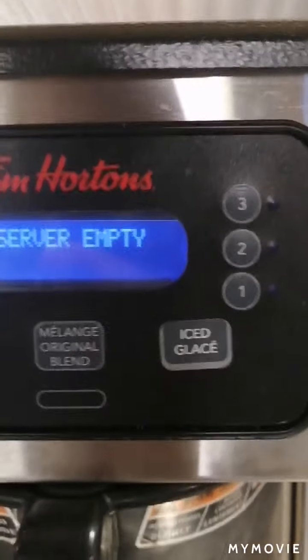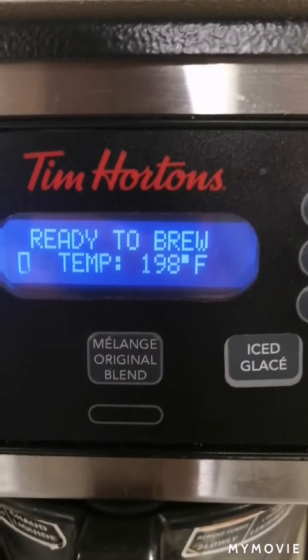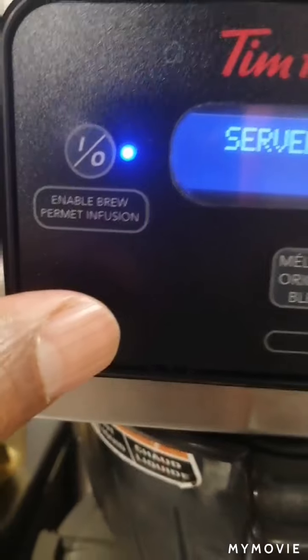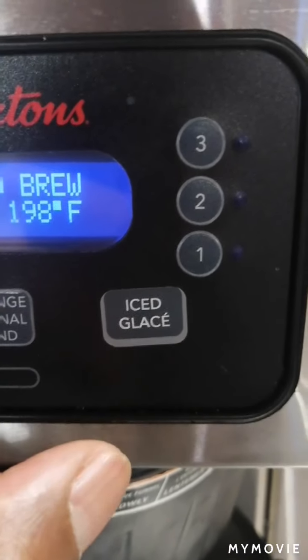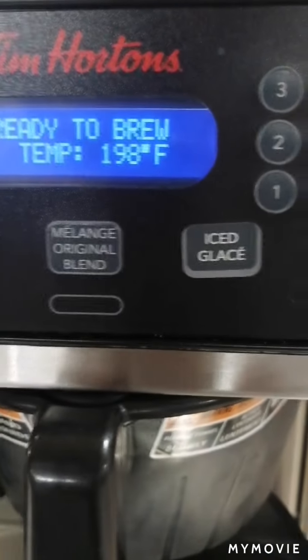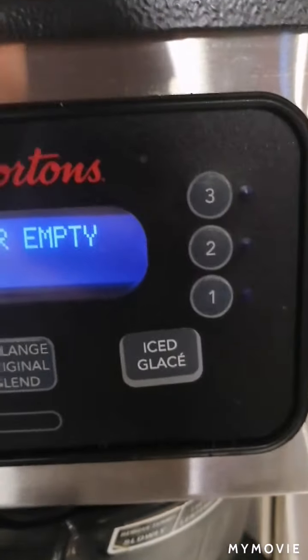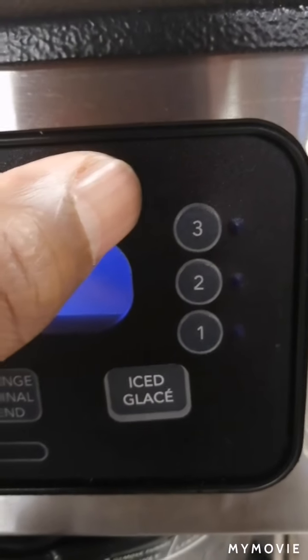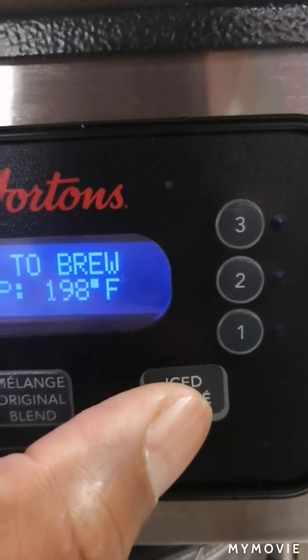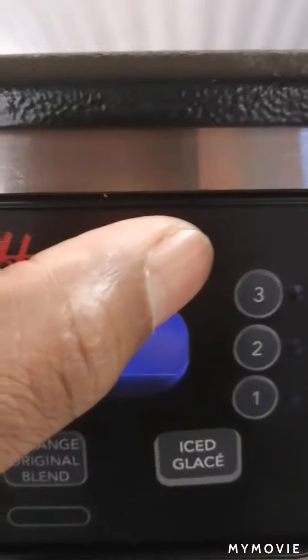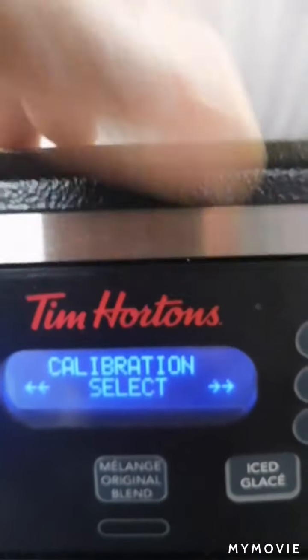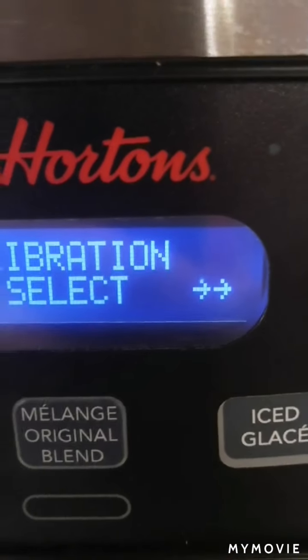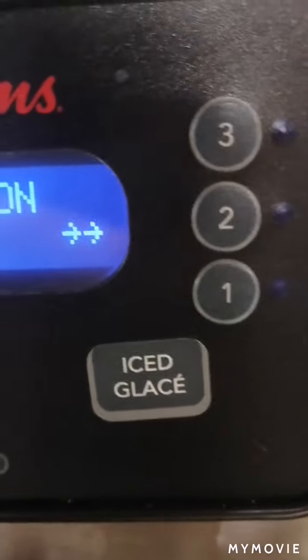The next thing you will do, you'll go to your machine, and there is a hidden button on the left and a hidden button on the right. There is also one at the left bottom and this one here that says ice, that one also. So the two buttons that we will focus on are the one on the right at the top and the one down here at the bottom. We will hold down this hidden button at the top until you see that calibration select comes on the screen. When that appears, you will select the button that says original blend.